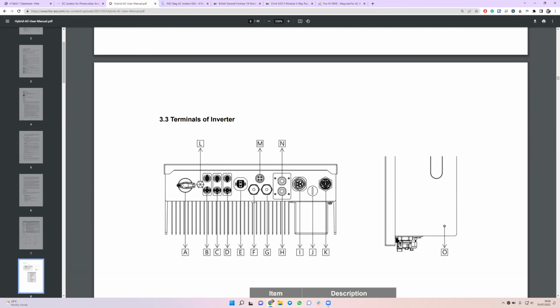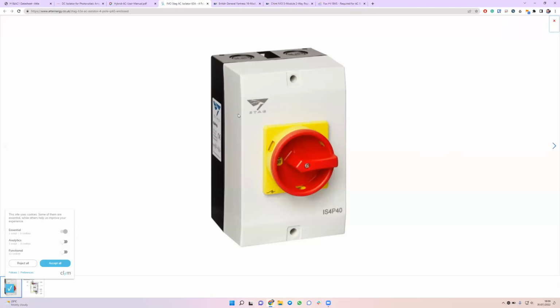Okay, so once you've isolated the DC, the solar is now inert. Great. Now we need to isolate the AC, or the alternating current, and that's the current that's coming from the grid going into your hybrid or your AC coupled inverter. Normally, again, you'll see installers will fit one of these. It's an AC isolator, normally yellow. The whole box sometimes is yellow. Yellow with a red turn handle is pretty normal. You'll want to turn that to the off position. It will make quite a clunk when it changes.